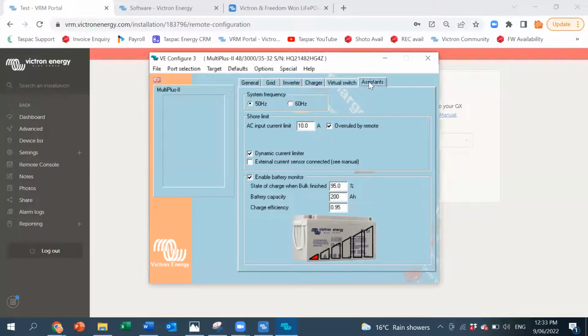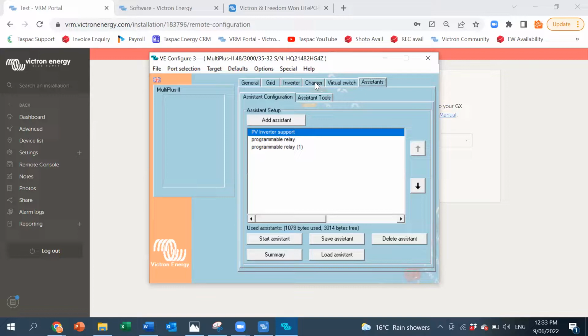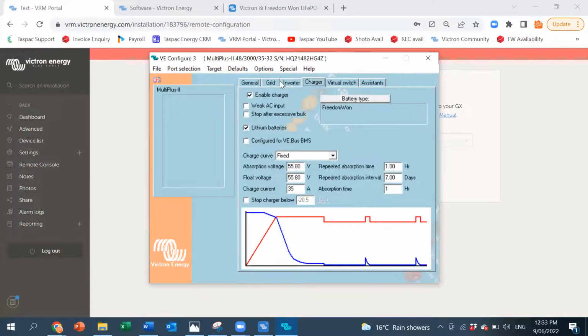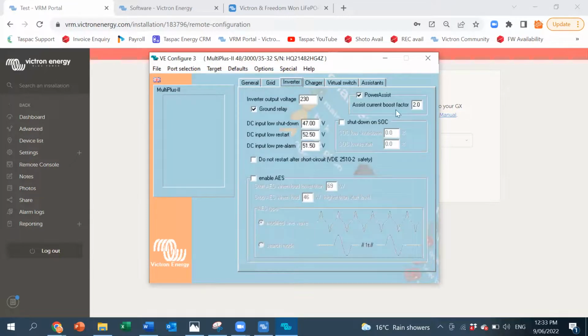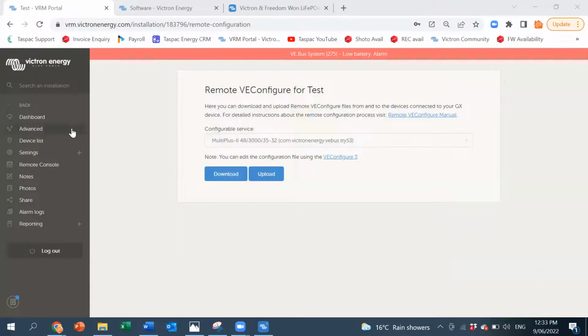Okay, so that's come up and we just check. Yes, we've got three assistants in there. Let's check the charging voltages and the discharge voltages. Yep, I'm happy with that. So turn it off, that's the inverter programmed. Don't need to upload that again.